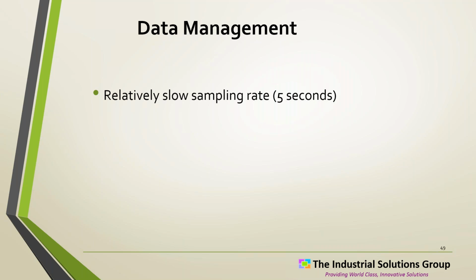And in the grand world of controls, most of this process equipment really doesn't tax these systems that much. Think of a packing line: a control system needs to go through in milliseconds, constantly adjusting. Well, process systems and utility systems are really, in the computer world, very slow sampling rates. Five seconds in my book would be a fast rate. You don't need that feedback that quickly, so you don't need to be spending a lot of money on the latest type of processor. And the big problem with a lot of data is you just keep getting more and more data, and now you have to worry about memory, although that's less of a problem now since the prices have come down so much over the years.